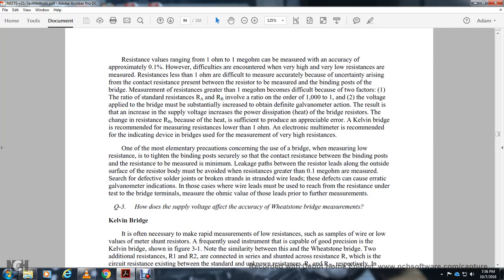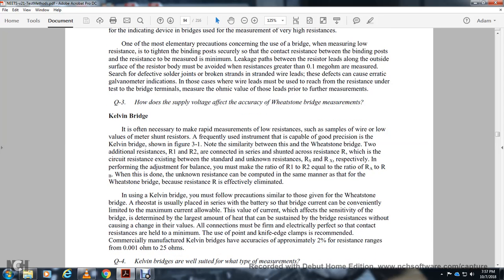One of the most important precautions when using a bridge to measure low resistance is ensuring secure contact at the binding posts. The minimum leakage path between resistances must be maintained. For resistances greater than 0.1 megaohm, surface leakage along the resistance body must be avoided. Erratic meter indications can result from poor wire connections. The ohmic value of leads should be measured prior to further measurement.